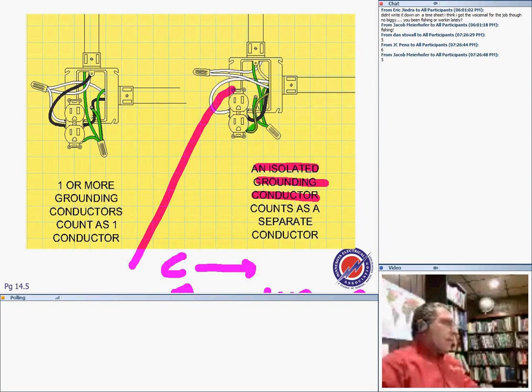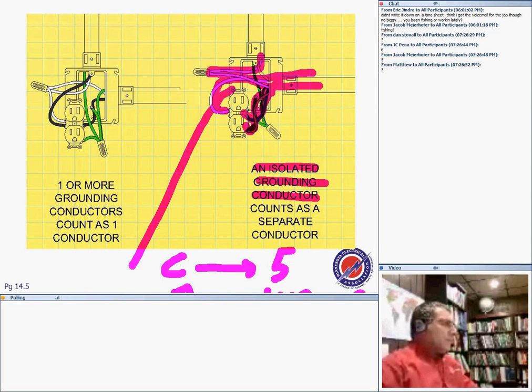All right, so count them. I have 1 coming from outside, terminating. Another 1 coming from outside, this is 2. The third one coming in is 3, right? And I have a hot, this is 4. I also have my isolated ground, this is 5. I have 5 conductors. For those who counted them as 7, if you add all of these, it becomes equivalent to 7 conductors.